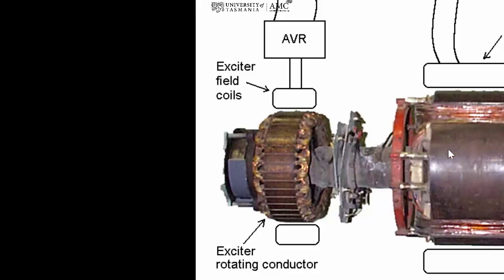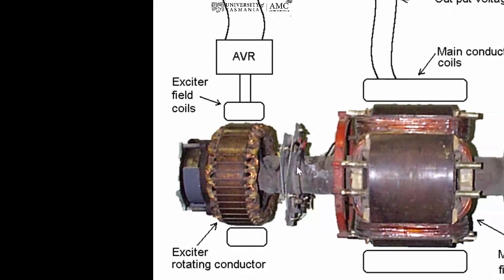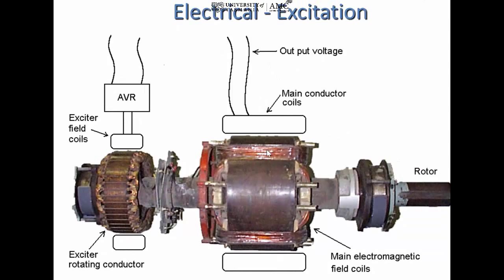So whereas the alternator has rotating magnetic field poles, the exciter has stationary field coils or field poles, and it has our conductor on the rotor. So this guy, as we said, produces the DC voltage for our magnetic field coils in the rotor, but the AVR is telling these field coils how much voltage to produce to keep these field coils generating the right amount of output. So this one's called the exciter, this one's the alternator.